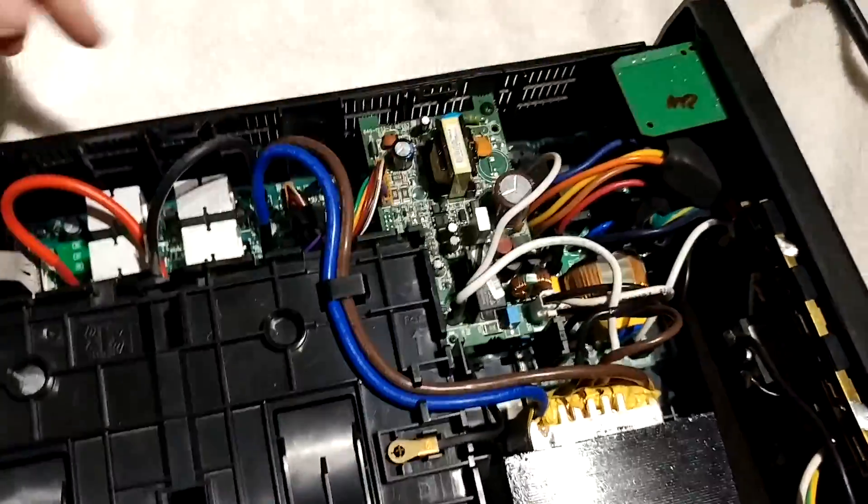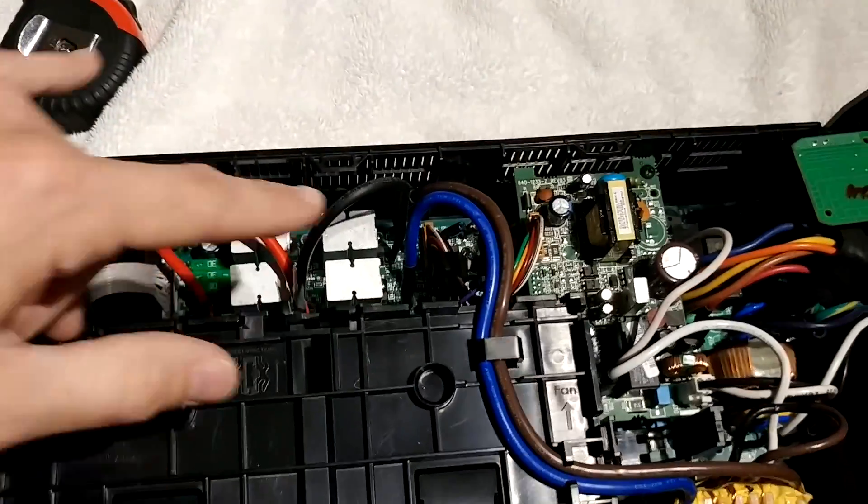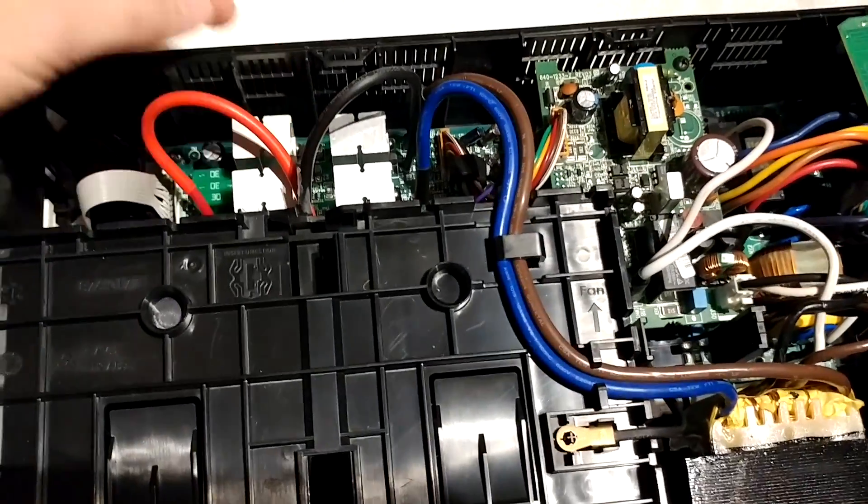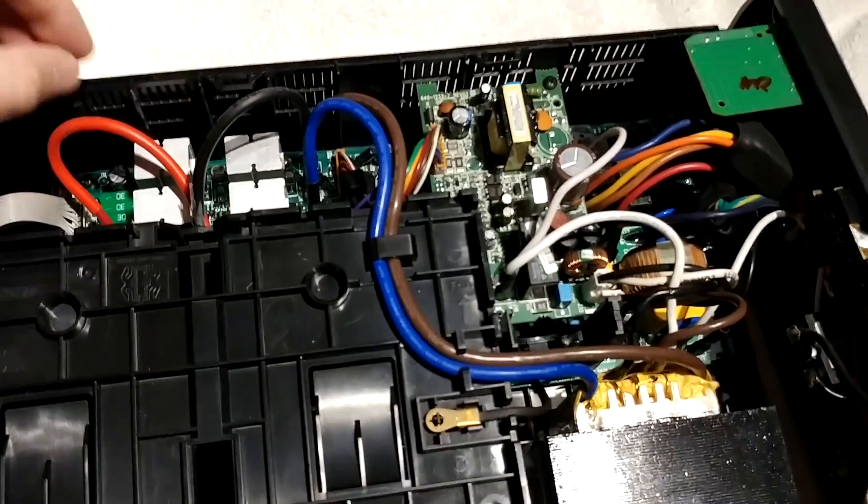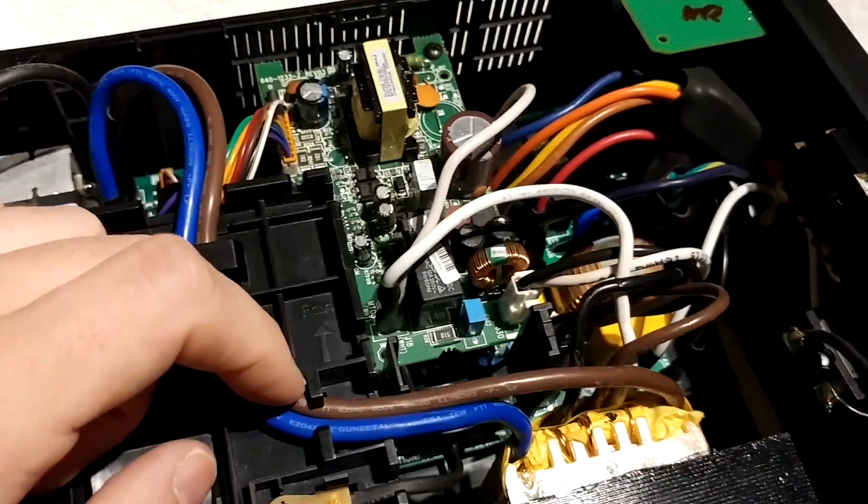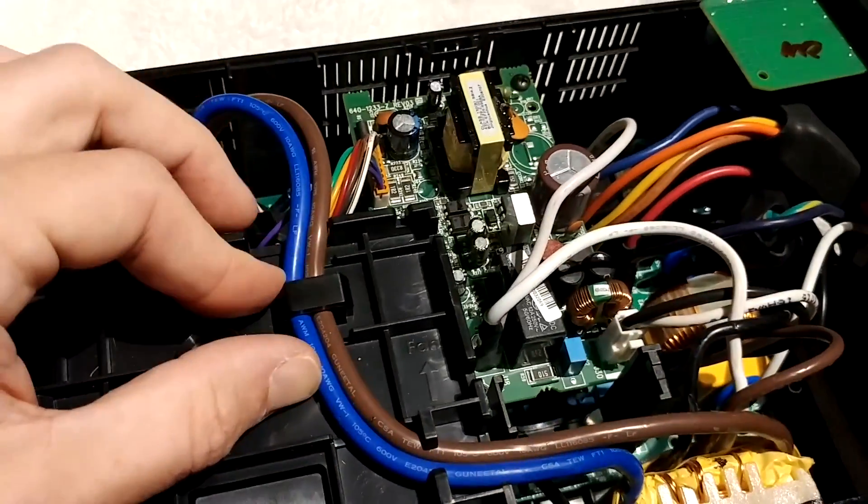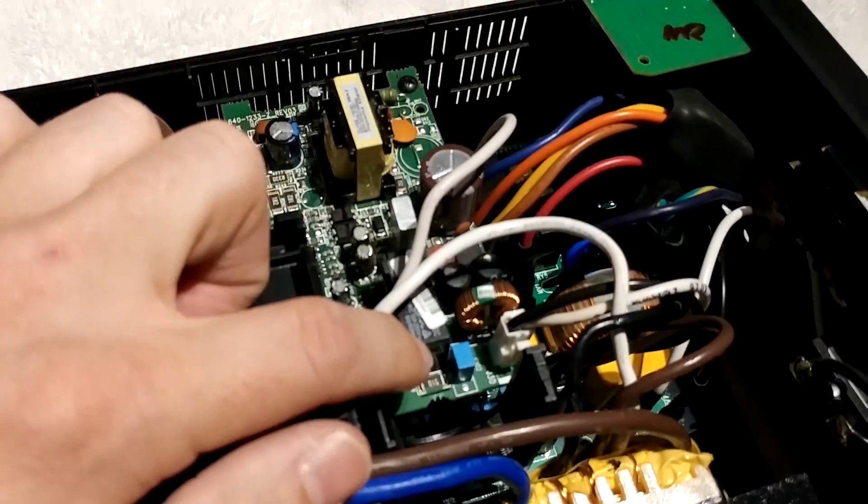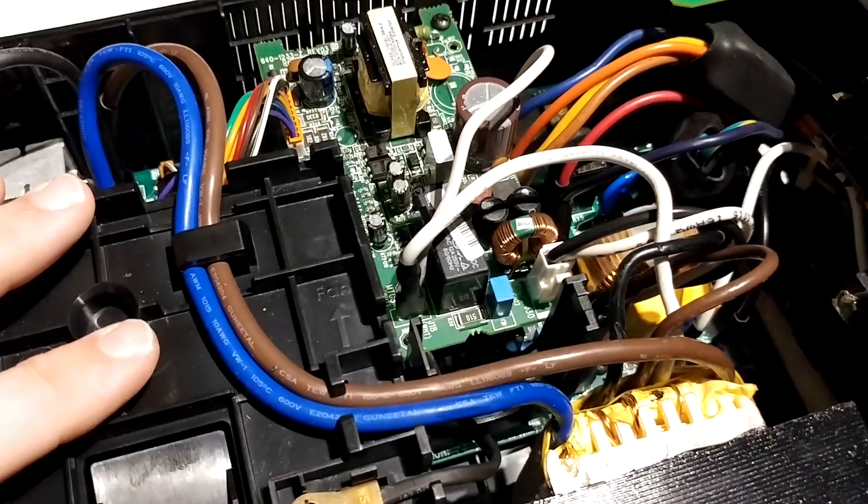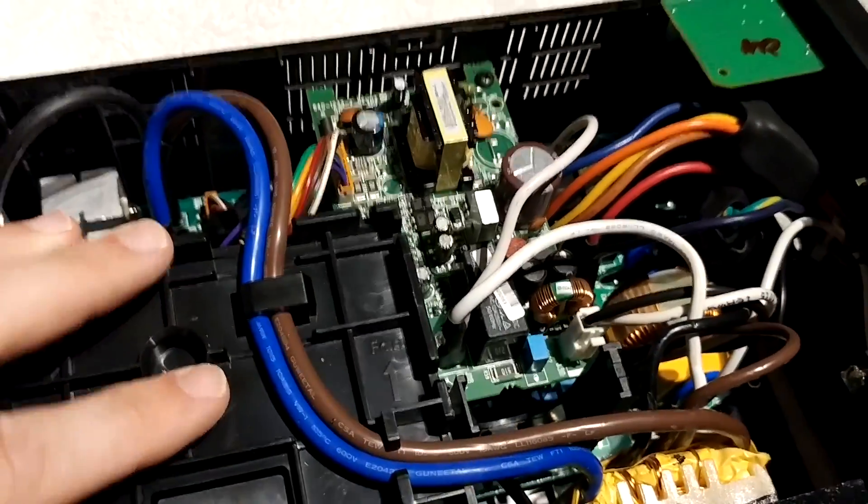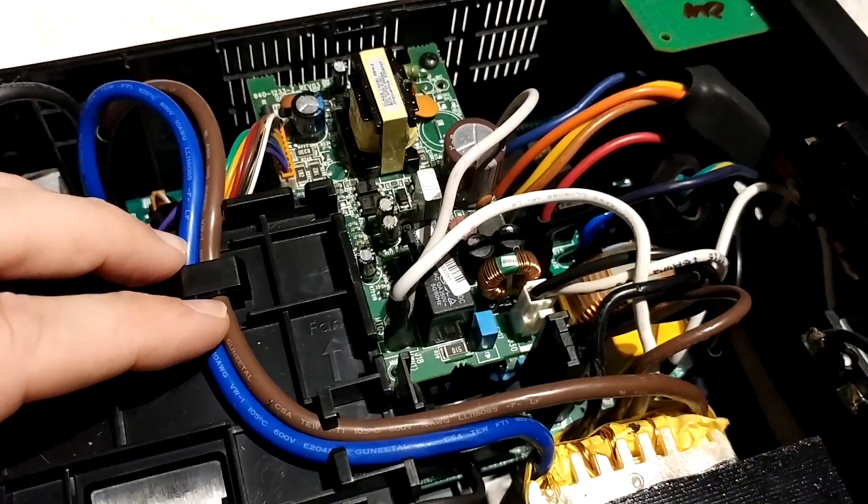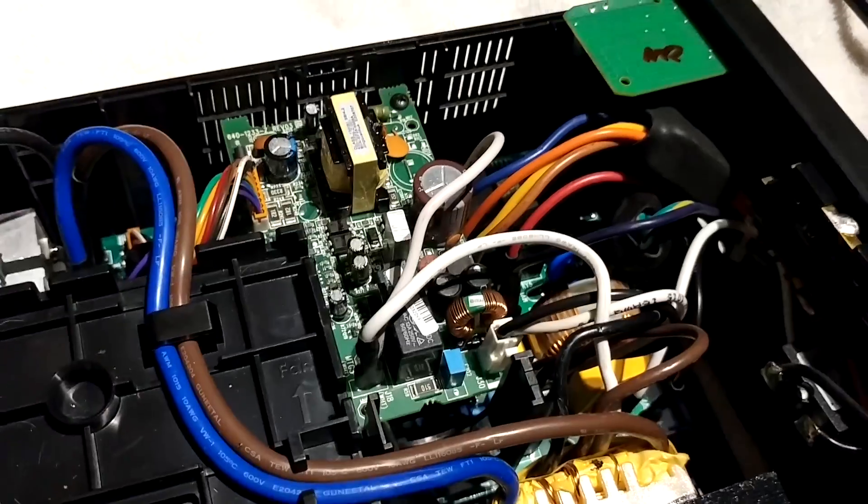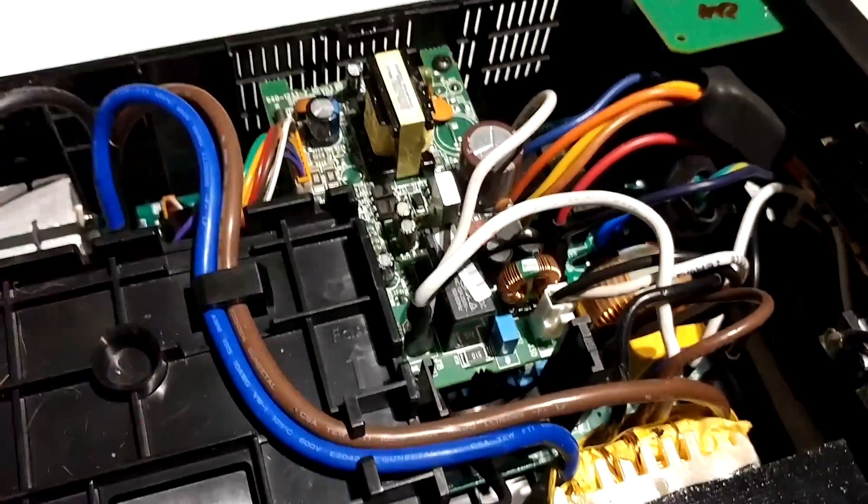The bottom board is held in with four other small screws. There's one back here, one here, one here, and one here. Once you disconnect all those wires, the bottom board will slide up and out. There are a few relays in here that might be the typical electronic component that fails, made by Omron, most of them. Here's one right here on this upper board. I actually sent an email to Omron asking them about the part number because I couldn't find a data sheet for these relays, and they actually said it was a custom part for APC. They're going to hopefully maybe get back to me with more details on this relay and maybe some specs and help me find a comparable part should I ever have to replace them.